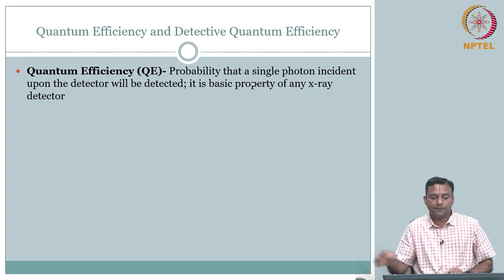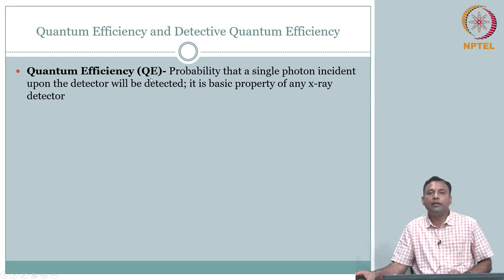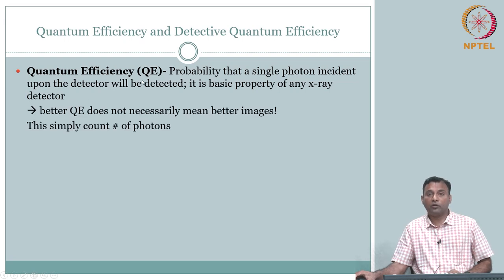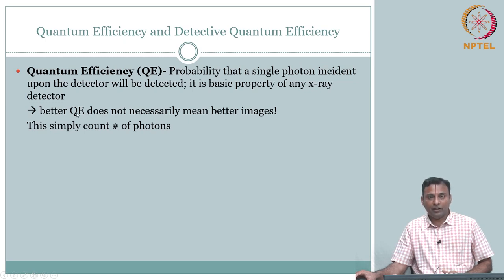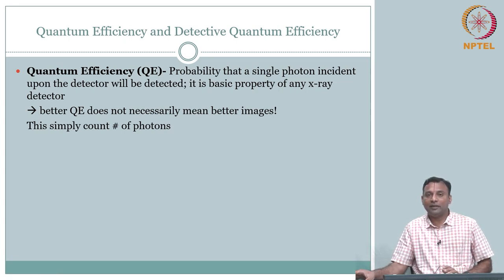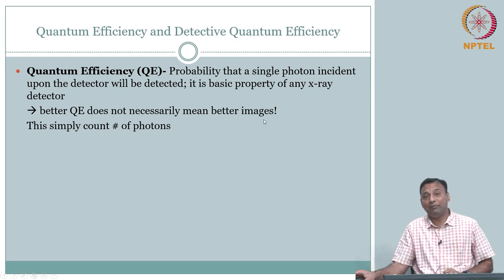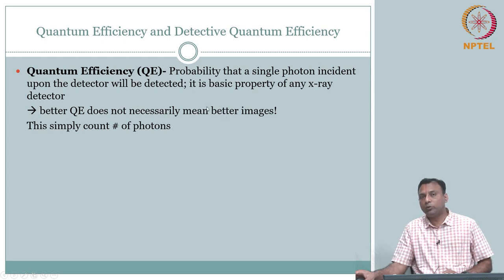Quantum efficiency is the probability that a single photon incident upon the detector will be detected — meaning it will interact with the material. It is a basic property of any x-ray detector. But does a better QE numerically necessarily mean better images? Better QE does not necessarily mean better images. If you have two detectors with the same QE but one converts and localizes photons with less randomness than the other, intuitively you want the one with less fluctuation.